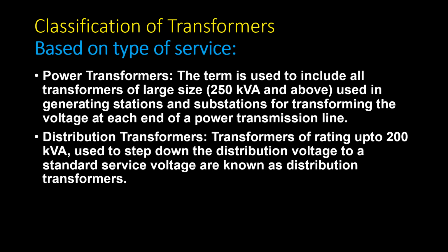If you are using single phase voltage, if your requirement is lower, then suppliers provide you single phase supply, and its rating is 230 volt, single phase, 50 hertz. That supply we generally use for residential use. So from 11 kV we need to step it down to either 230 volt or 415 volt. For that purpose we need a distribution transformer, and the transformers installed on double pole mounted substations in your premises may be of 200 kVA or less than that.